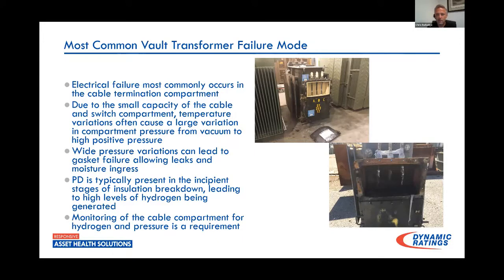Now, the interesting thing about this compartment is there's no real means for maintaining it. The cable compartment is typically filled with oil. There's nowhere to really take a gas sample unless you take the plug out, in which case you've lost your gas sample. You can do some oil sampling from the drain if you want to run DGAs. But another interesting thing about this compartment is it is the only compartment on the transformer that is not normally pressurized. So you're not aware that you have a leak with this one, or it's hard to be aware that a leak is happening. Typically, these are just cables coming from outside the transformer into this compartment, and they're terminated where they go into the switching section of the transformer.